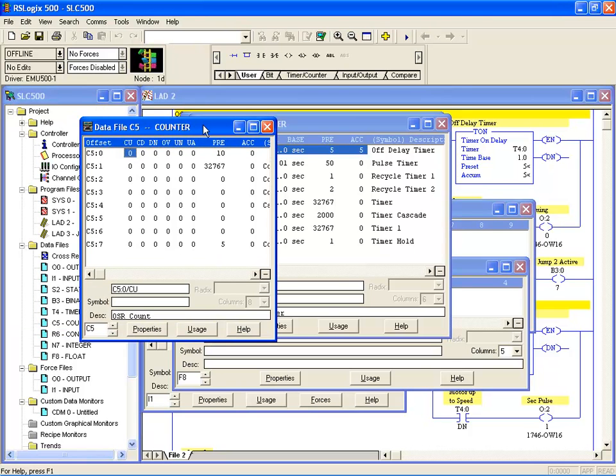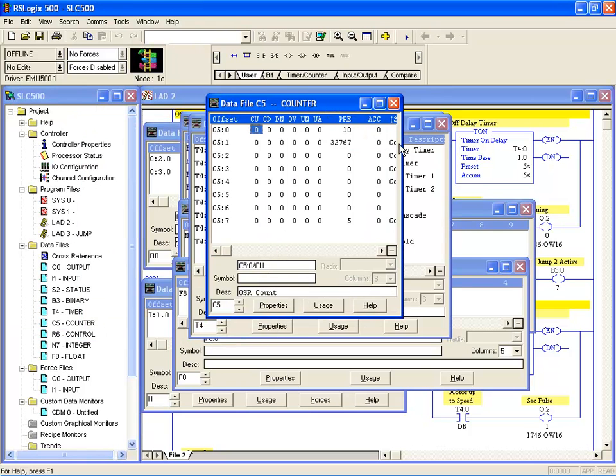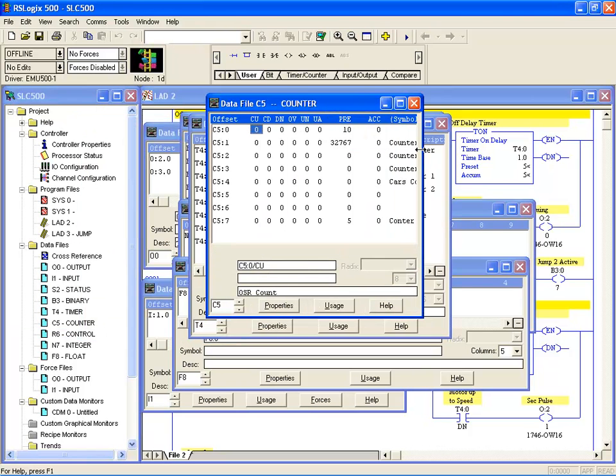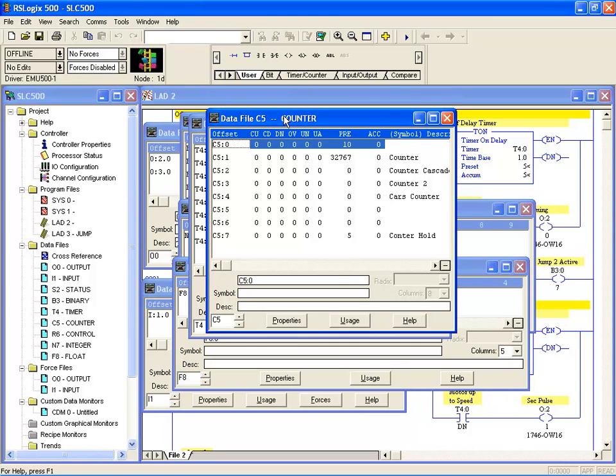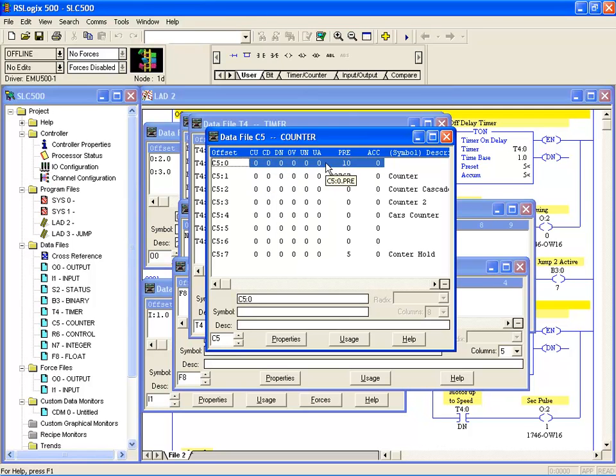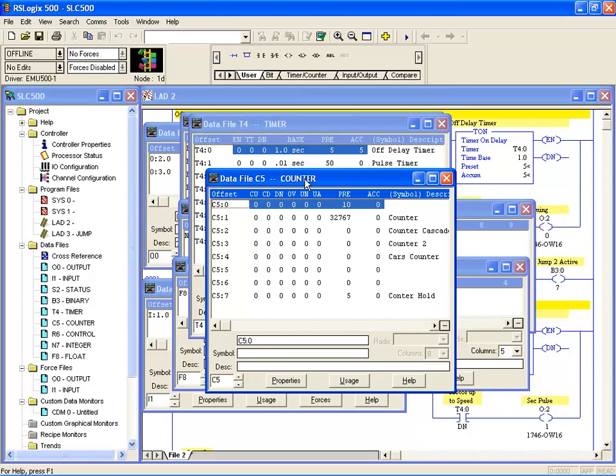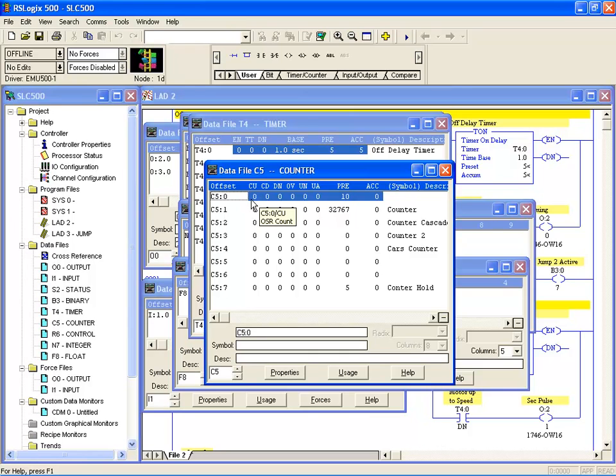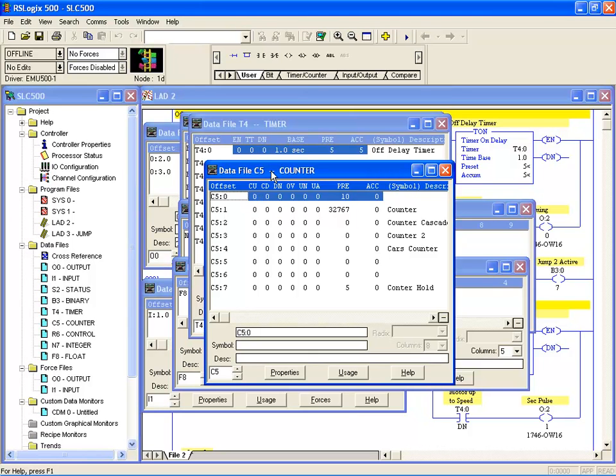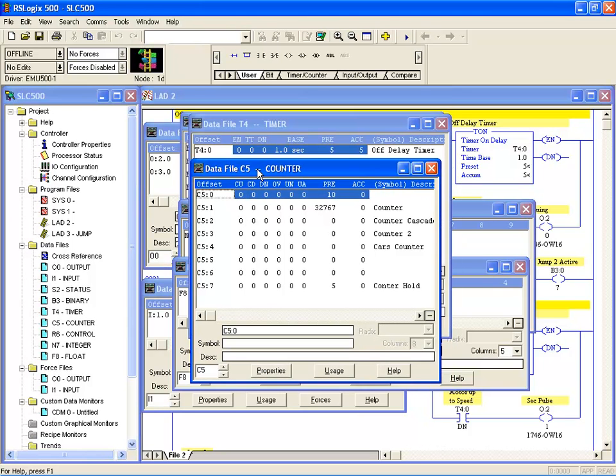We have a similar situation where we have status bits. Let's look at C5:0. We have status bits, a few more status bits in the counter element, a preset and accumulator. So we have one word for the accumulator, one word for the preset, and another word for the status bits. Now you may be thinking, what happens to the other parts of those status bits? Well they're just not user addressable. So the only part of that status word available to the user is the one shown in the data file. That's a good summary of word and bit data and memory in the SLC.